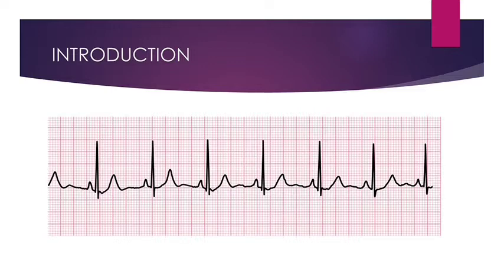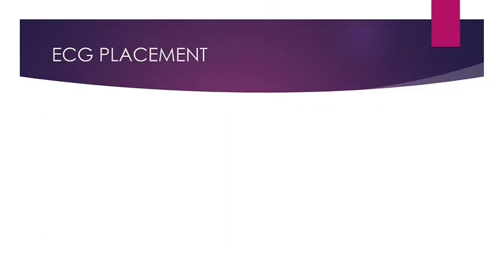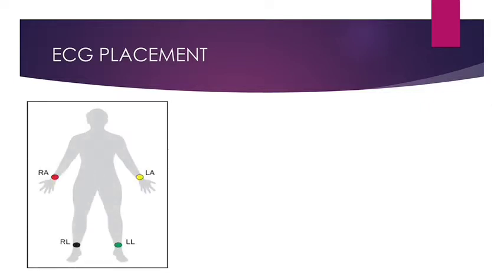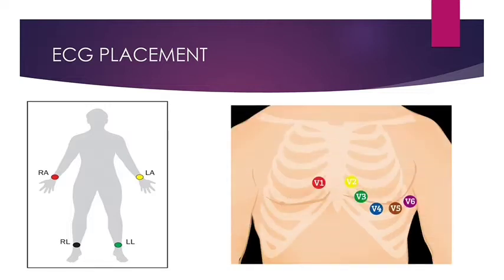Now what are the ECG placement sites? Mostly 12-lead ECG is used in clinical practice. Ten electrodes are required to produce a 12-lead ECG. First, 4 electrodes on 4 limbs: right arm has a red color cord, left arm has yellow, right leg has black, and left leg has green. Then 6 leads on the chest: V1, V2, V3, V4, V5, and V6.